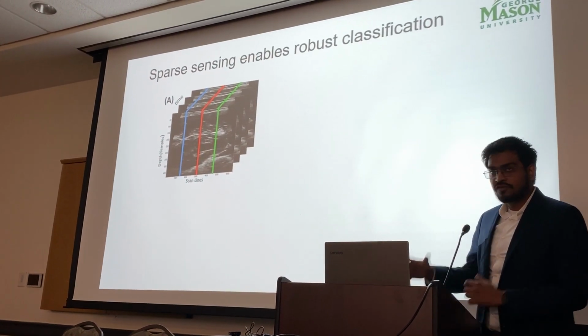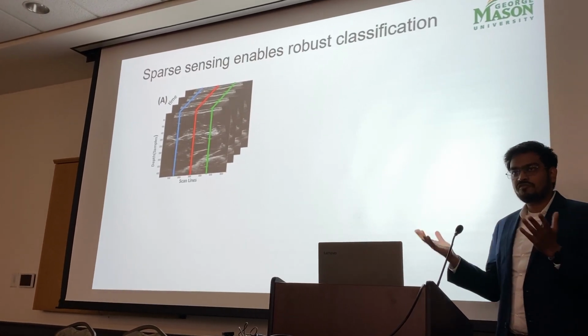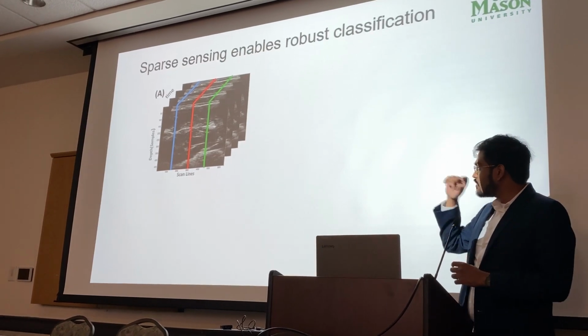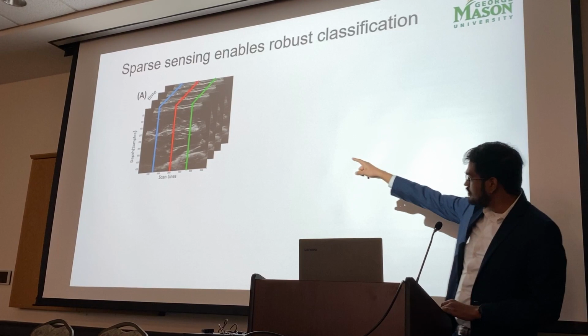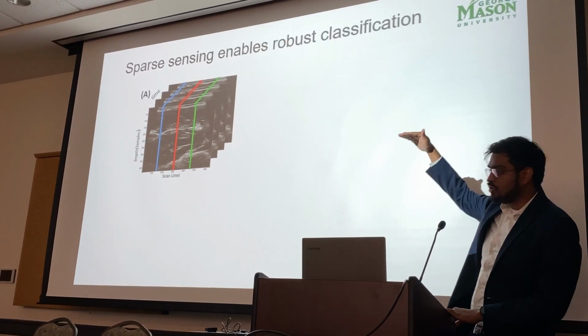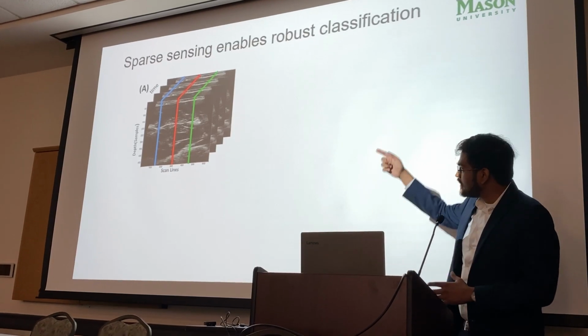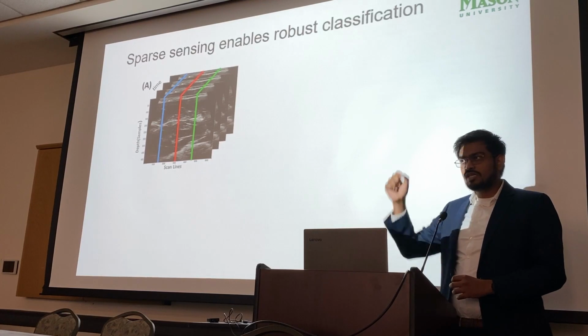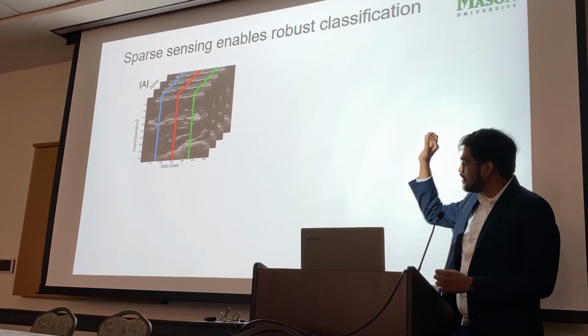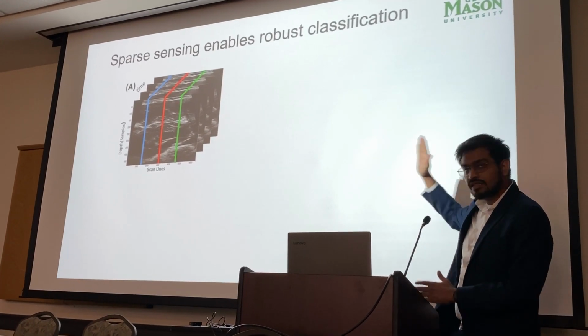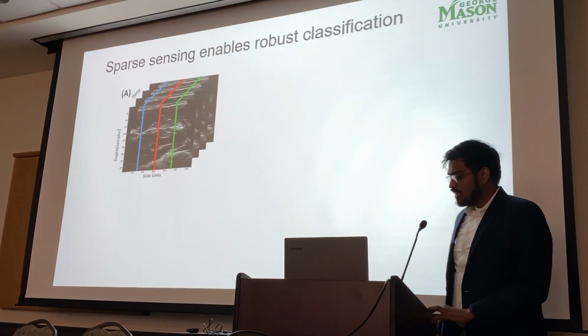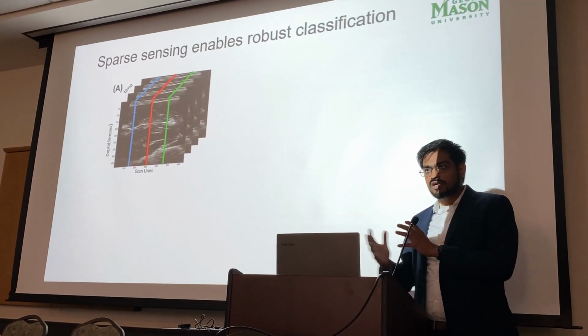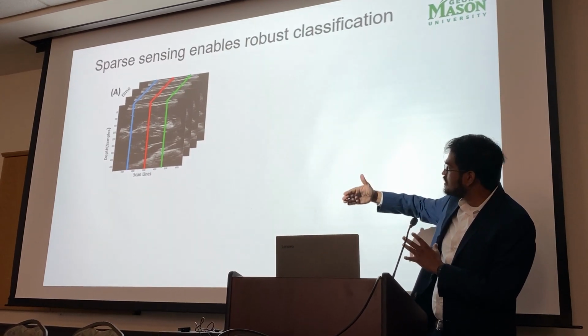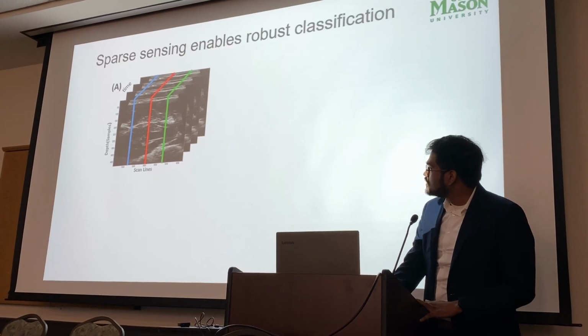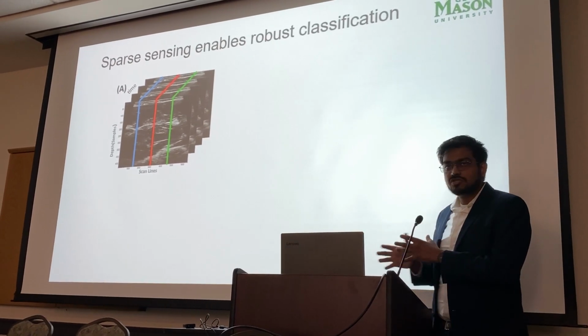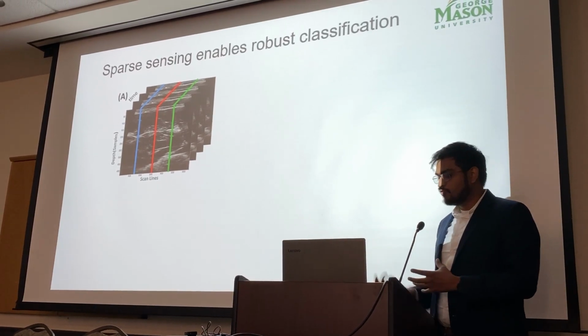So in order to understand the first problem, can we pare this down to a few sensors instead of 64 sensors, let's look at what a typical ultrasound image looks like. You have depth on the y-axis, so you're looking down through the layers of tissue into your body. And on the x-axis, you have the individual scan lines, or the individual elements that have passed ultrasound signals into the body, and you stack them together, and you get this nice, beautiful image. Now, as you're scanning through the body in time, you get stacks of images, and we call these stacks a cine loop. As you stack more of these images together, you get a nice cine loop that shows your muscles moving.